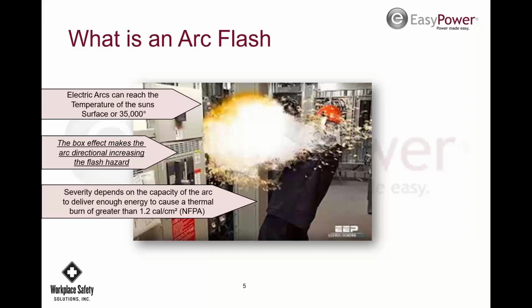That's an important number to know, because that's what our arc flash boundary is. Once you go inside that boundary and go over 1.2 calories per square centimeter, you need to have a shield and arc rated clothing at a minimum. And then you have to calculate what it is at your working distance, where you're actually going to work, and when you're actually closer to that arc flash. Then you need to calculate that so you can gear up your PPE to that level.